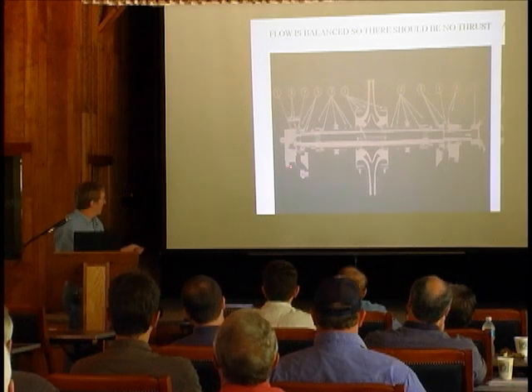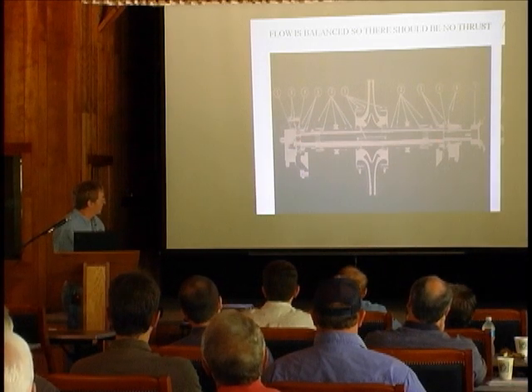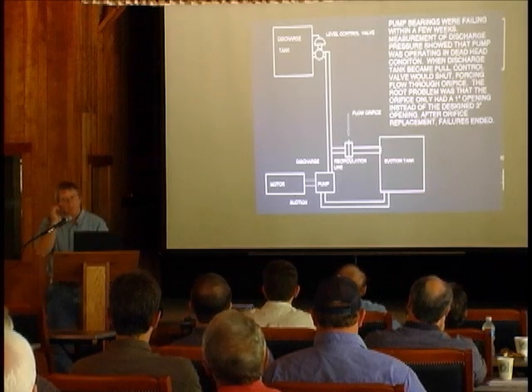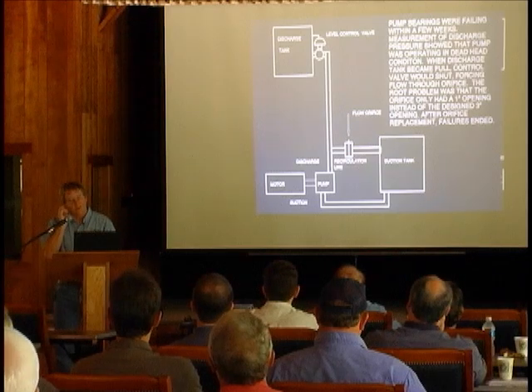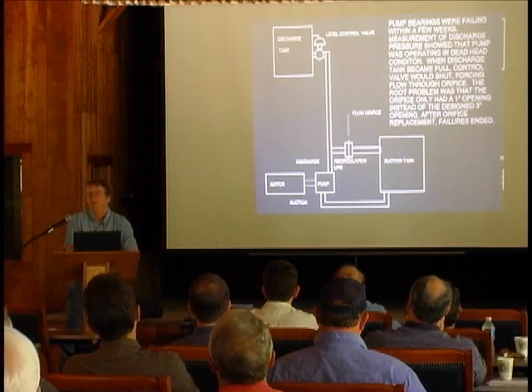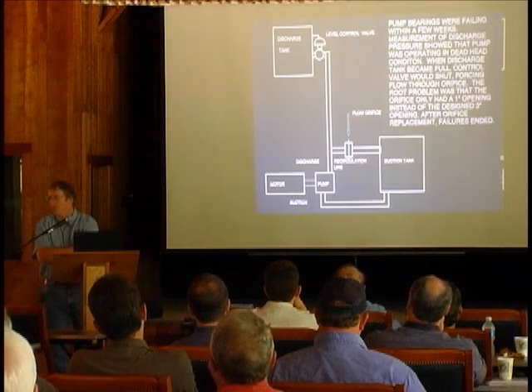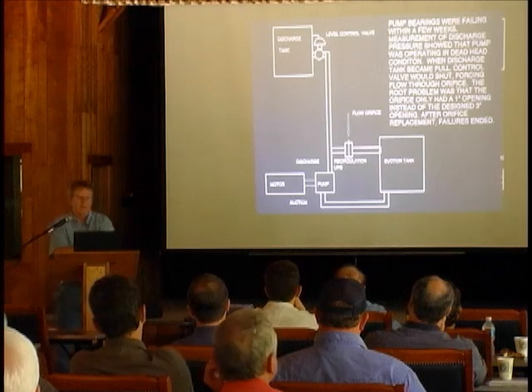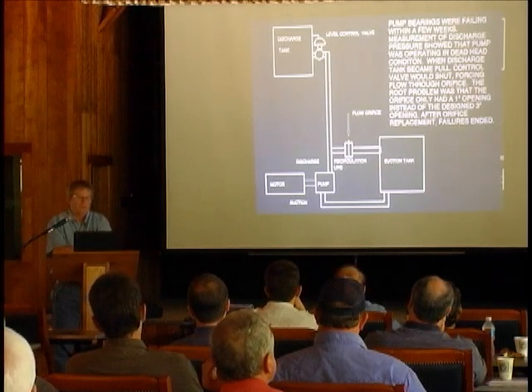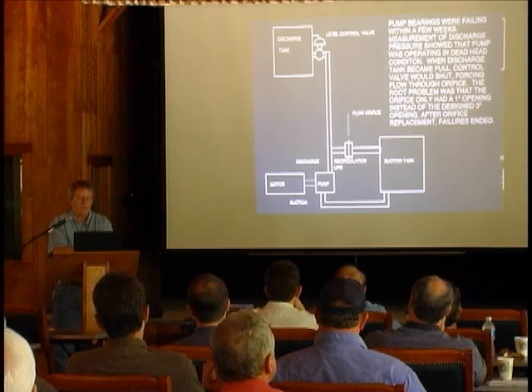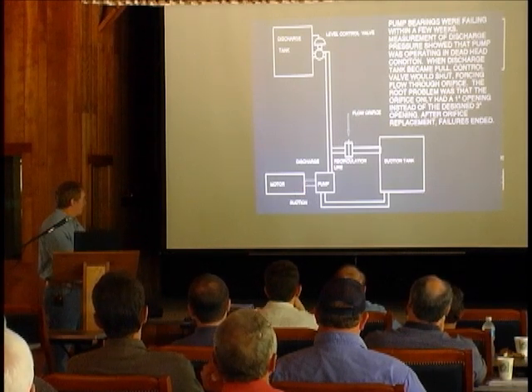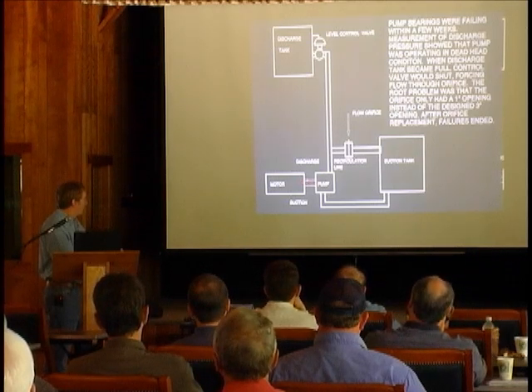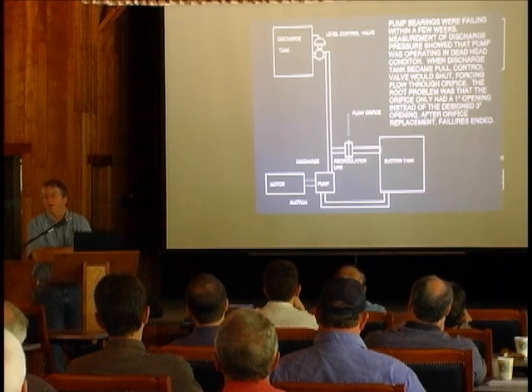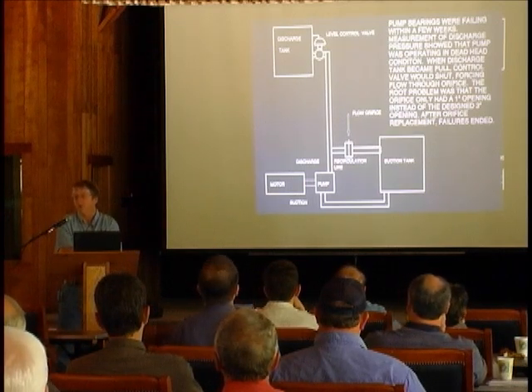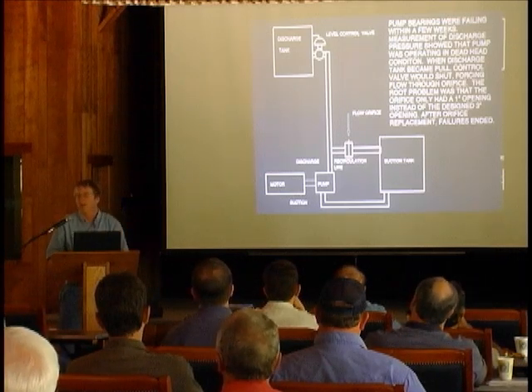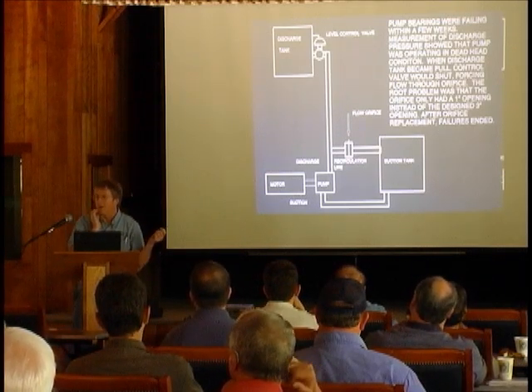So these bearings were failing on this particular pump about every 6 weeks. And the odd thing is we had 3 pumps here. On 2 pumps, they run forever, and on 1 pump, every 6 weeks, the bearings would fail. So I took the spectrum analyzer out, and I didn't even take it out of its box. I looked at the pump, and you can see the shaft jumping back and forth right here, and that's called axial shuttling. That's a sign that a pump is operating against too much back pressure; it'll sit there and vibrate. And I said, wow, your pump's probably operating against too much back pressure.